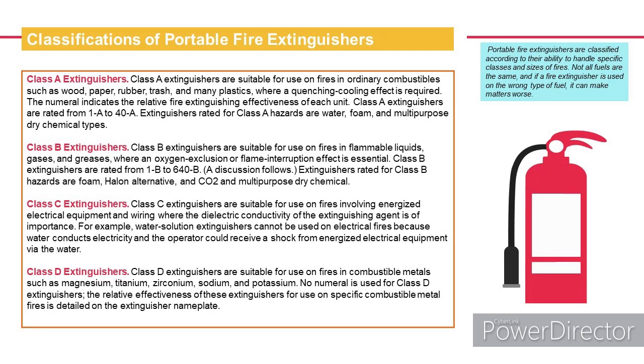The numeral indicates the relative fire extinguishing effectiveness of each unit. Class A extinguishers are rated from 1A to 40A. Extinguishers rated for Class A hazards are water, foam, and multi-purpose dry chemical types. Class B extinguishers. Class B extinguishers are suitable for use on fires in flammable liquids, gases, and greases, where an oxygen exclusion or flame interruption effect is essential. Class B extinguishers are rated from 1B to 640B. Extinguishers rated for Class B hazards are foam, halon alternative, CO2 and multi-purpose dry chemical.